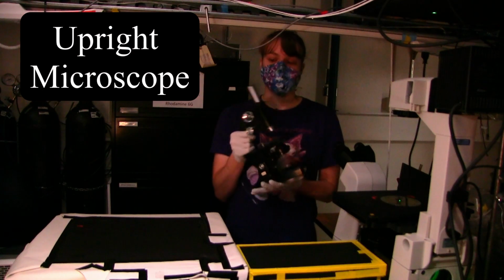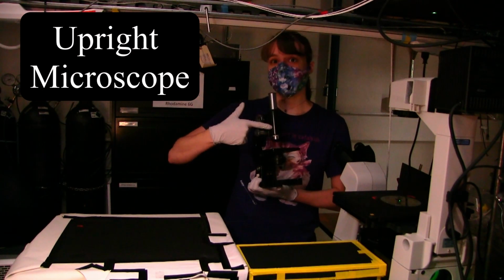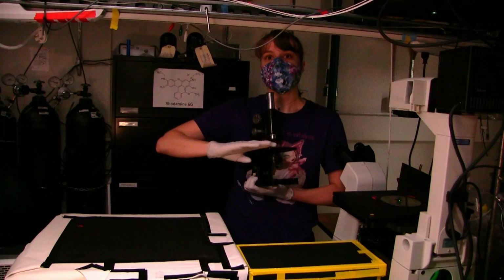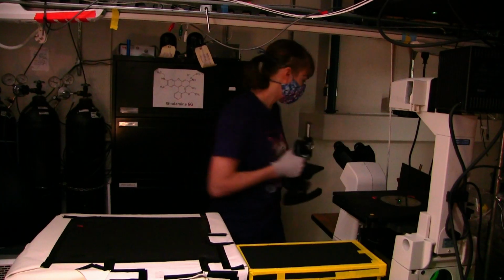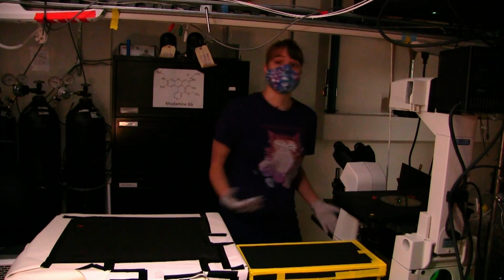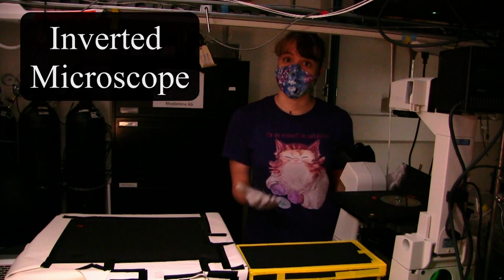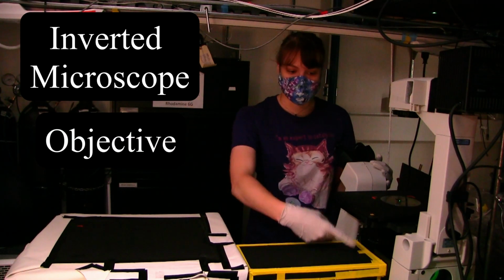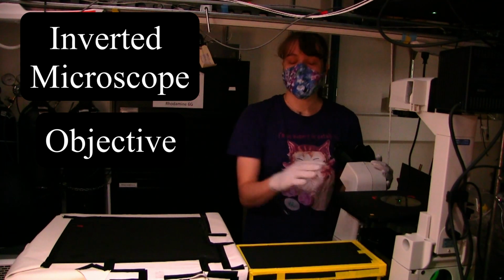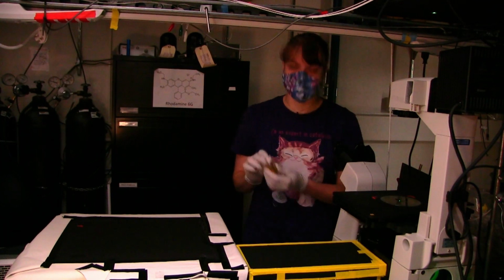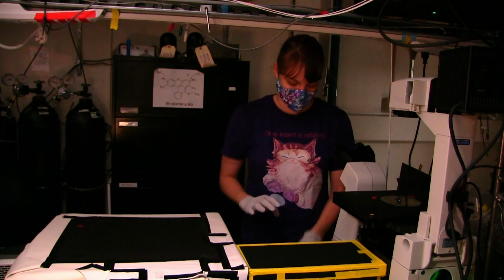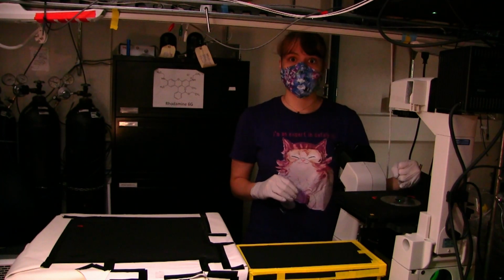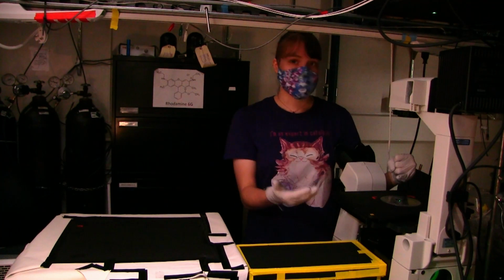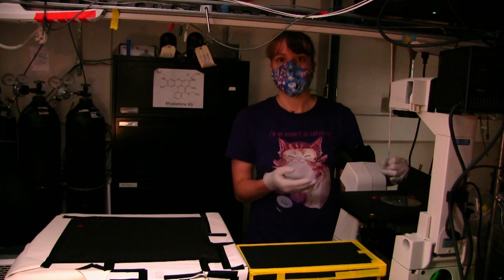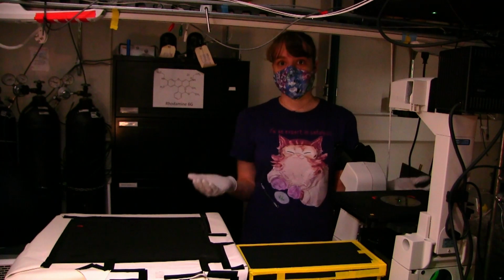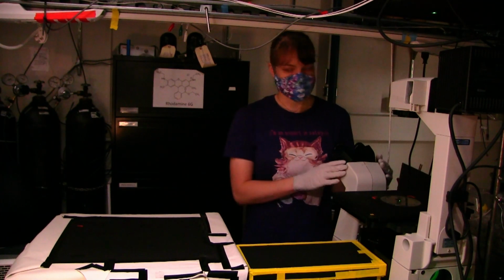This microscope is called an upright microscope. It has a lens piece and then an objective which focuses light onto our sample, which is on the sample plane here. In contrast, this microscope is called an inverted microscope because the objectives, housed here, are underneath the sample plane. The reason that we do this is because we want to look at our sample in solution. So here we have a cover glass with a solution of our sample on it, and our objective pushed up against the bottom of the cover glass. This allows us to see the sample without dipping our objective into the solution.